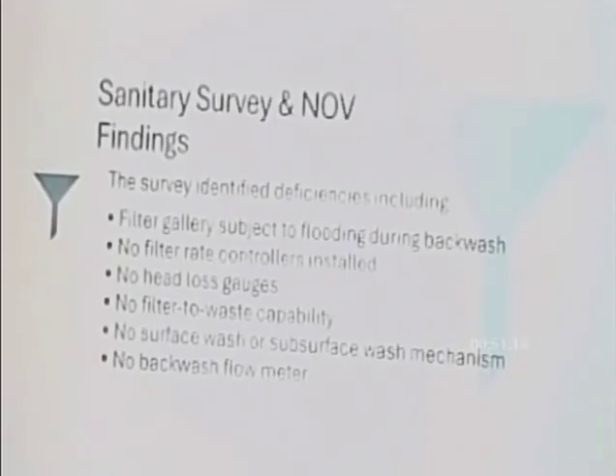Well, over time, that basin underground has lost capacity, and there's just not a good way to keep that cleaned out. So now when we do filter backwashes, it starts backing up into that filter gallery, which is part of the reason we don't have electric actuated valves in the basement. They're using hydraulically actuated valves because that's a little bit better than electric actuated valves when it does have water. But that's a problem for obviously being able to backwash for the full 15 minutes that DEQ wants.